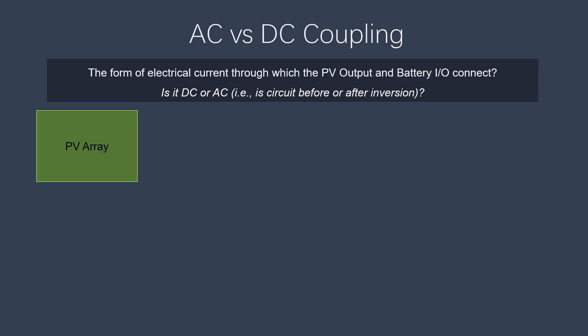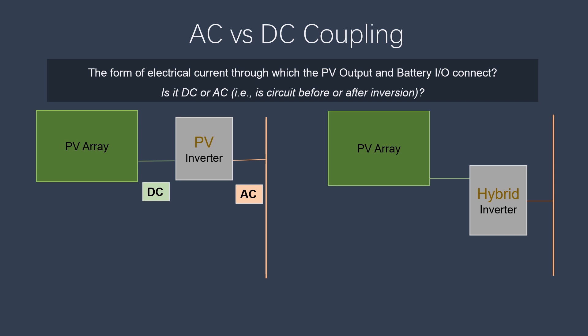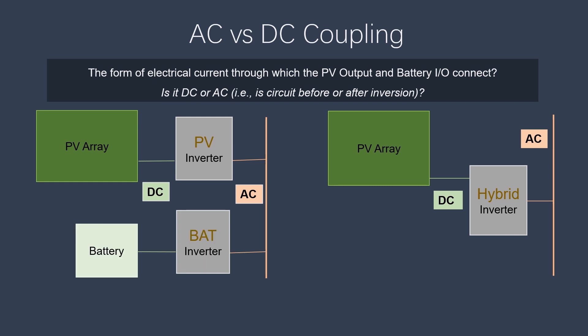Let's look at both couplings side by side. On the left, we have a PV array connected to a PV inverter, with DC and AC components. A battery is connected but it cannot be connected straight to the PV inverter — it must go through a battery inverter, and therefore the connection between the PV and battery is through an AC bus bar.